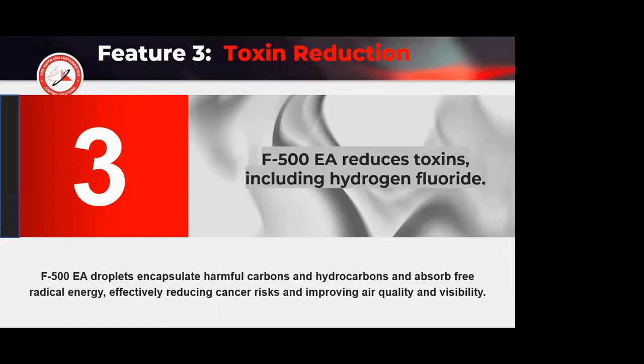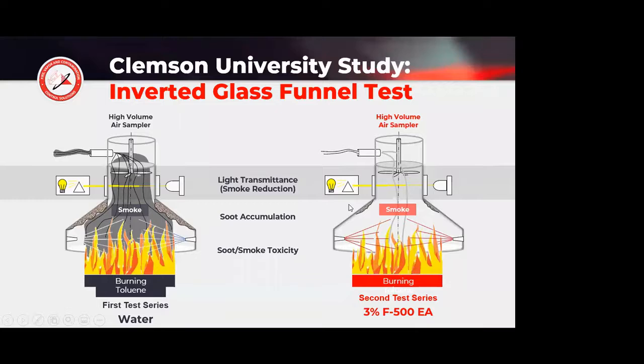The third feature is this interruption of free radicals. And as free radicals come together, sometimes it's referred to as combining or coalescence. That's what causes the toxic soot and smoke. So think of free radicals as they join together, they're forming the toxic soot and smoke. So we had Clemson University, their environmental division, run some tests. So they set up this plenum over here, have a light source, a light on one side, and a light receiving source on the other side of the chimney.